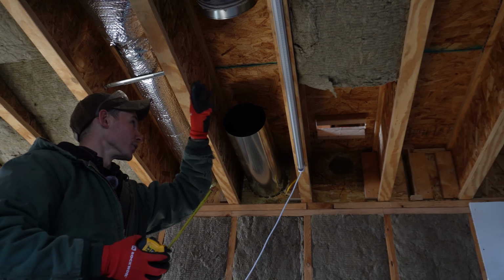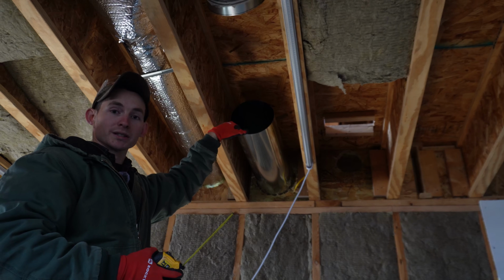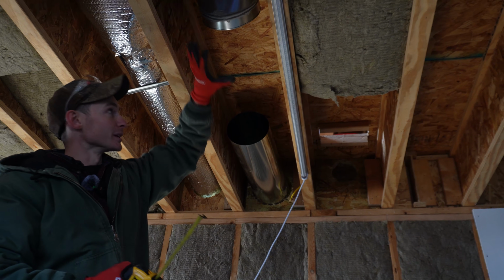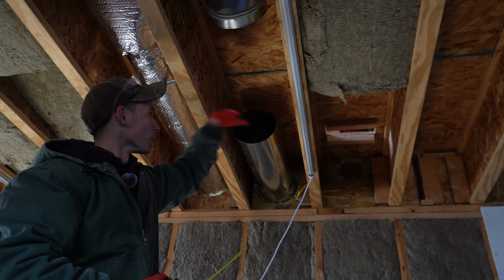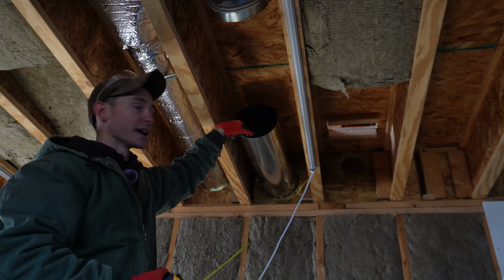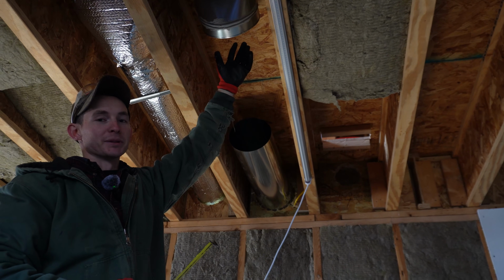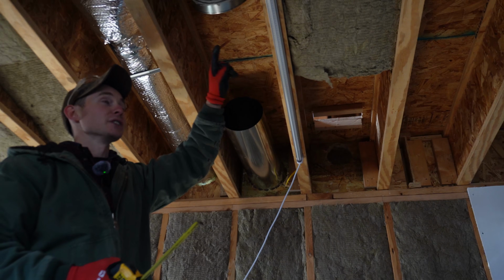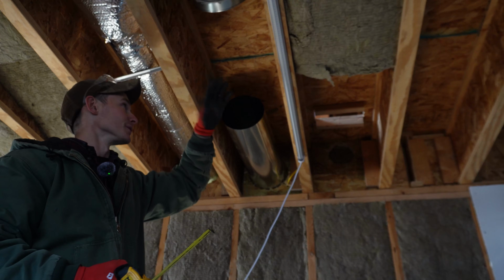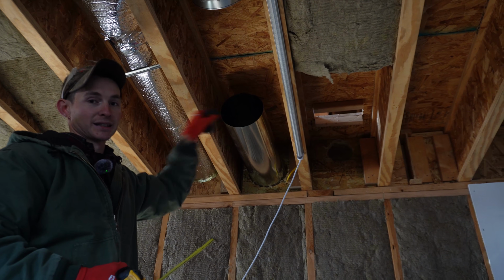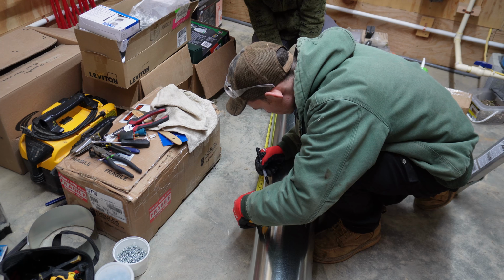In general, the crimped end should be pointing towards the airflow. This is a return, so the air is coming down and going that way, so we want all of the crimped ends pointing that way. But with the boots, they're not really meant to be crimped going into a duct pipe, so in each run there's at least one joint where it's against the flow. But in general, best practice is to point the crimps towards your airflow.